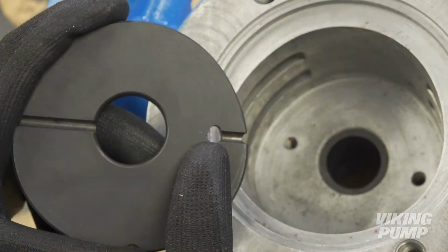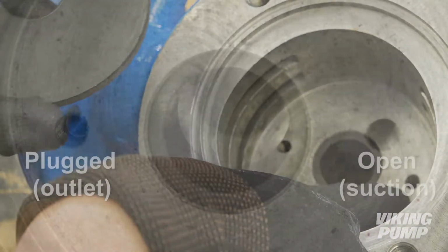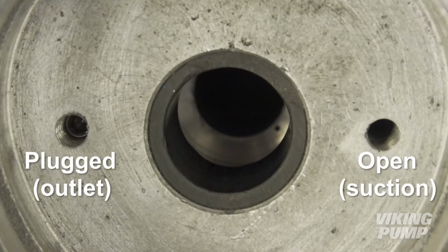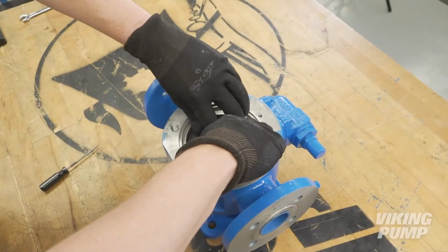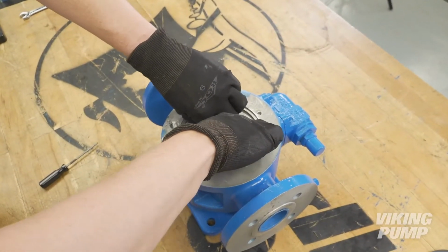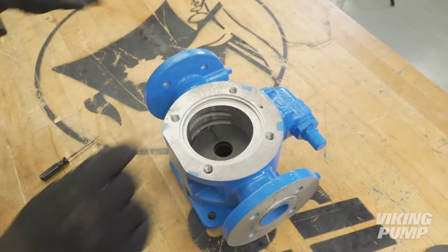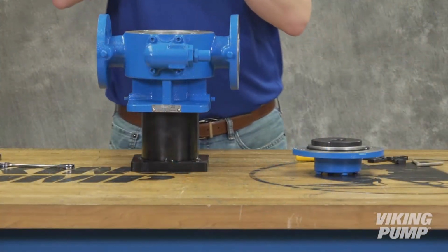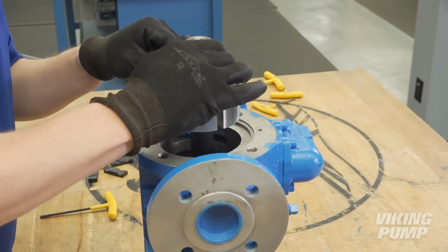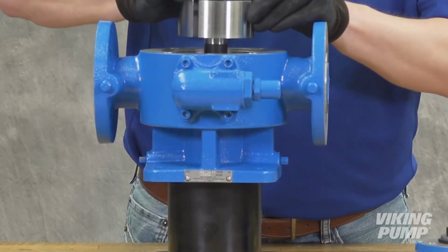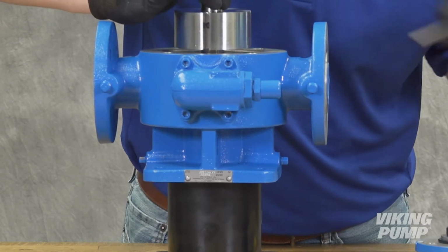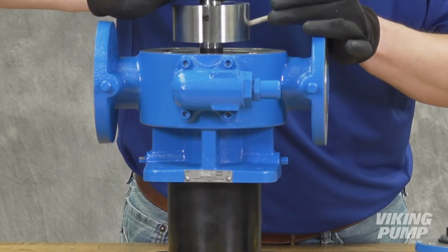Install one carbon disc into the casing. The hole should align with the open hole on the suction side of the casing. The other hole should be plugged. If the disc should get jammed, don't force it. Pull it back out, confirm that it's aligned correctly, and try again. Coat the shaft with compatible lubricant and install into the casing. Just before the rotor is fully installed, insert the push rods. Once the push rods are installed, you may finish installing the rotor.